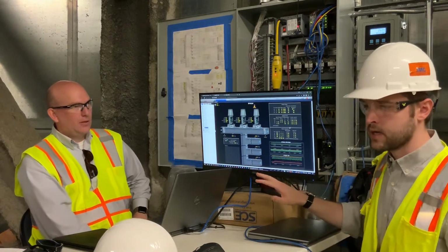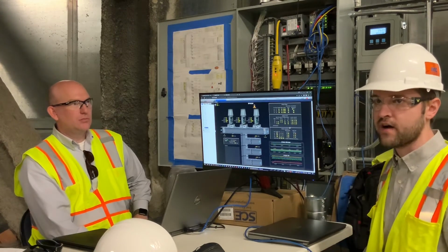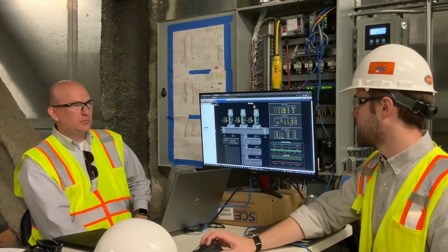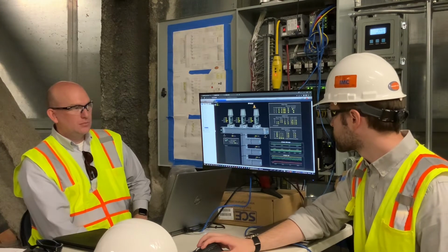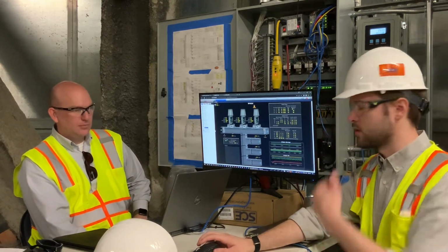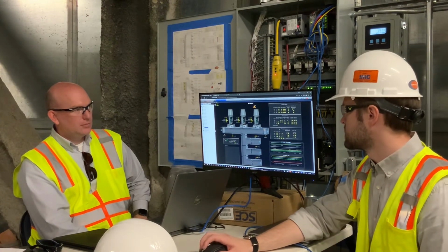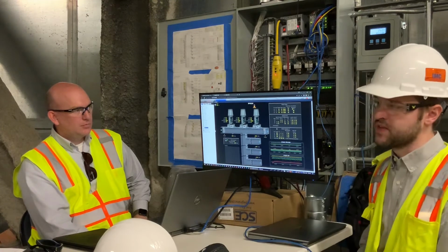Stage 3 is your backup. Stage 1 is always on. Stage 2 will come on when stage 1 is over 95% for a certain amount of time. Right now we have that, I think it's 3 minutes at the moment. It needs to be on for 3 minutes before it'll bring on stage 2. And then this last block here, this determines the sequence of your fan.